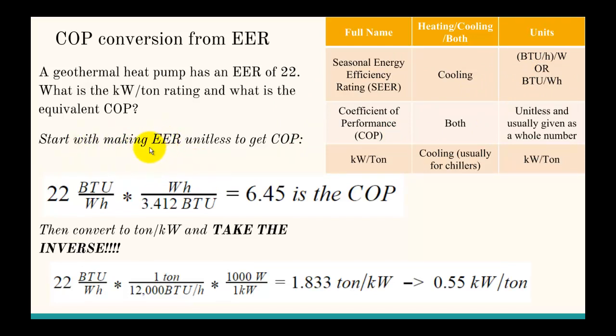We're going to start with making the EER unitless to get the COP. Basically we're trying to cancel out the BTUs and the watt hours. What's nice is we have our unit conversion that 3.412 BTUs equals one watt hour, and that cancels out the watt hours and the BTUs and makes it unitless. So we get that 6.45 is the COP.